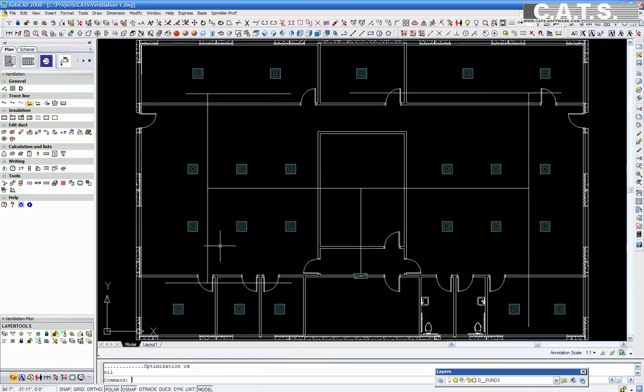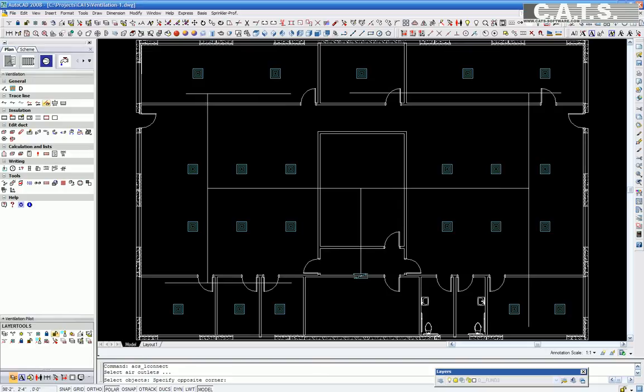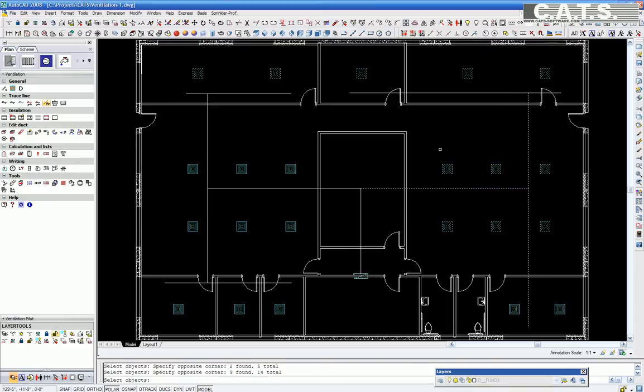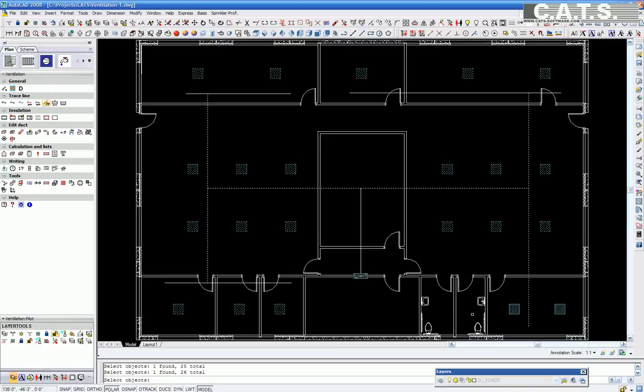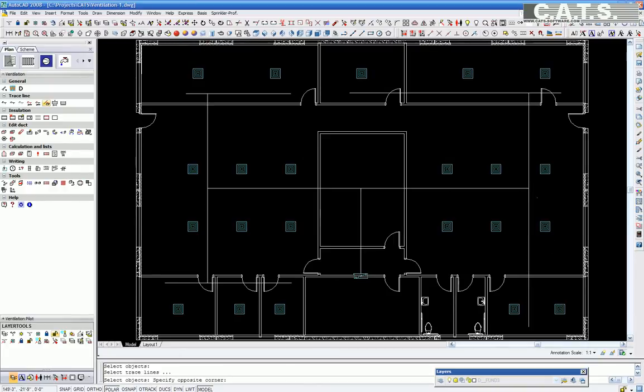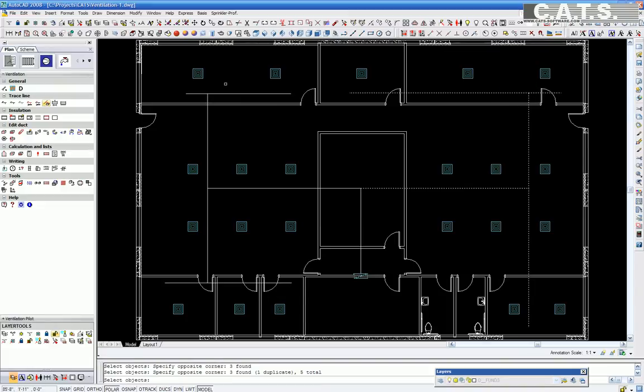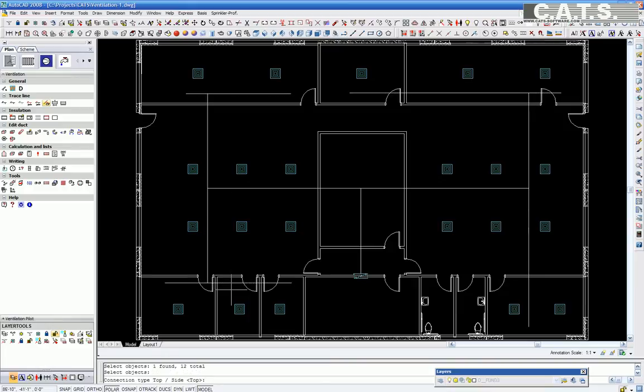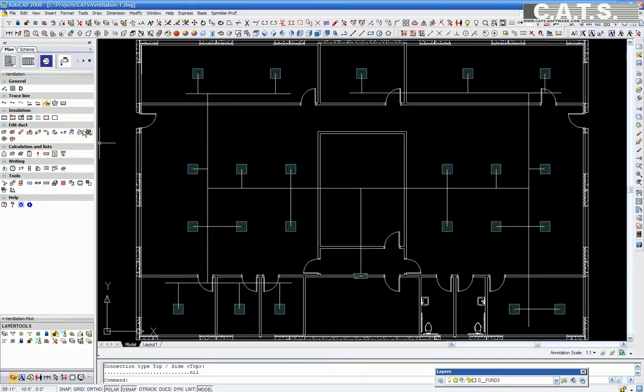Now we are connecting our diffusers automatically to our trace line. In the AutoCAD command, we are asked to select the diffuser. In this case, we select all diffusers. Next, in the AutoCAD command, we are asked to select the trace line in which the diffusers will be connected. In the AutoCAD command, we are asked whether to connect the diffuser on the top or the side. We will select the top. And now all connections between the duct center line and the diffuser are completed.